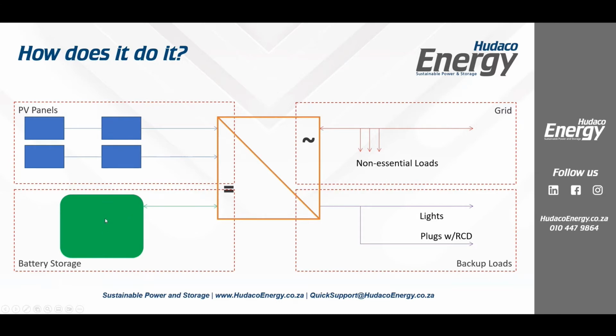I want my battery to cycle because it's cheaper for me to use my own energy than it is for me to buy more energy in from grid. However, I'm aware and I accept the fact that we've got load shedding happening at the moment. So don't go below 40% while grid is present. Of course, the moment grid falls away, in other words, the moment we lose voltage here, the inverter puts up an E10 error message, which basically just means loss of voltage, or they call it grid outage. This block, so we just set a number of 40%, but it could be whatever you set it at. This reserve state of charge block falls away, and the rest of the battery will function completely normally to carry all of our loads.